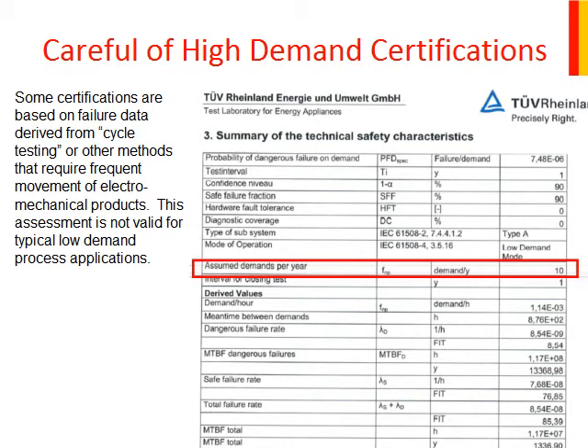There's a question: right above the red line, it says 'low demand mode.' I can only assume the analyst didn't really understand the definition of low demand, because 10 demands per year violates the definition of low demand in IEC 61508 and 61511. So those two lines do contradict each other, and I have no explanation for that.